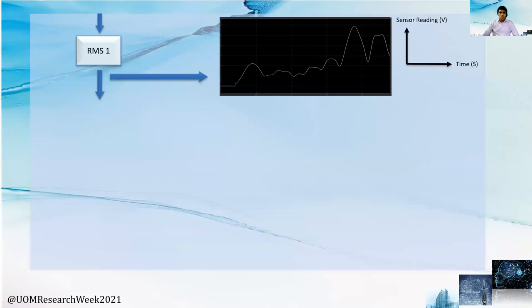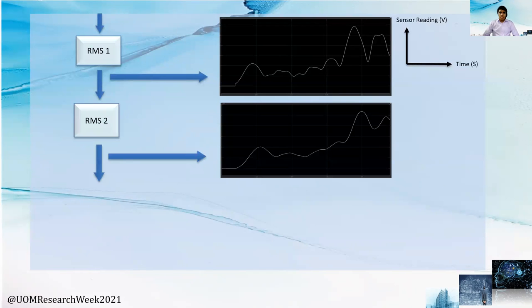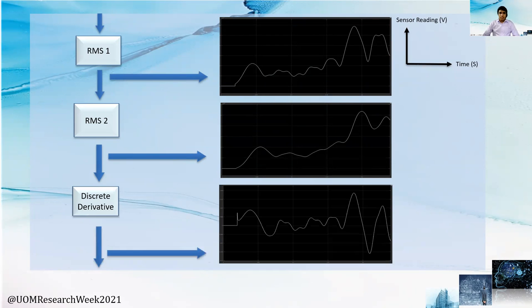Then, we send this data set through two cascade RMS functions with a fundamental frequency of 50 Hz. Our intention is to minimize the oscillations of the signal to make it convenient for decision making and data extraction. After that, we take its discrete derivation function to neglect any steady-state condition, as we are concerned about sudden variations in the current flow at any fault.